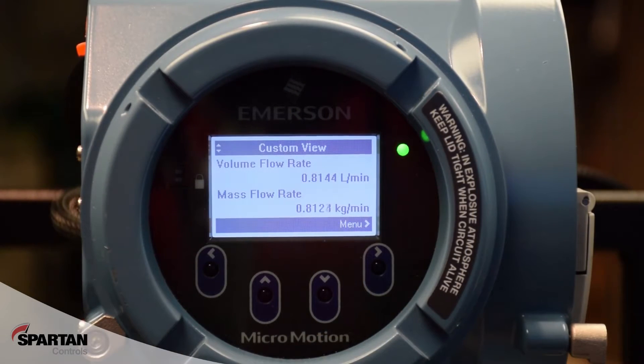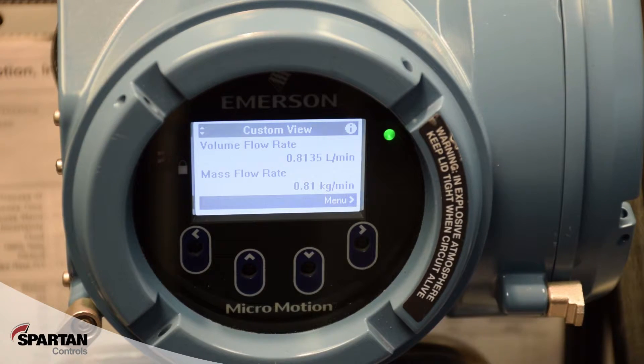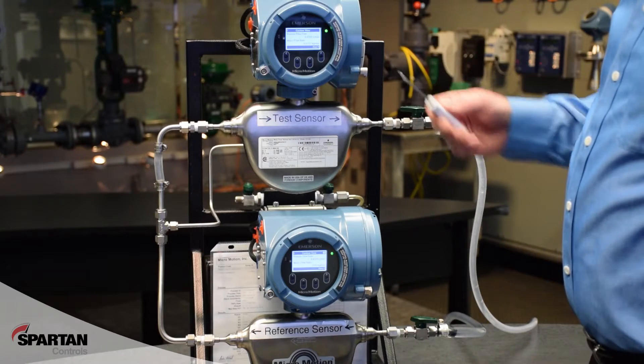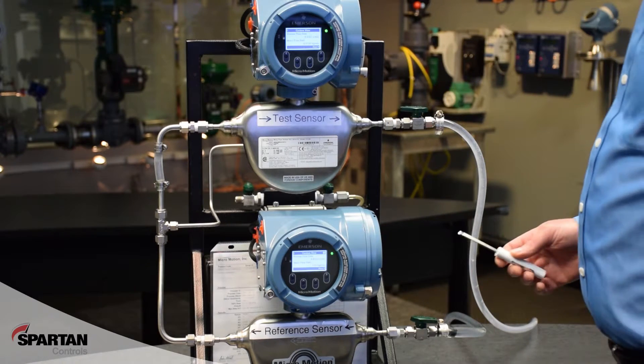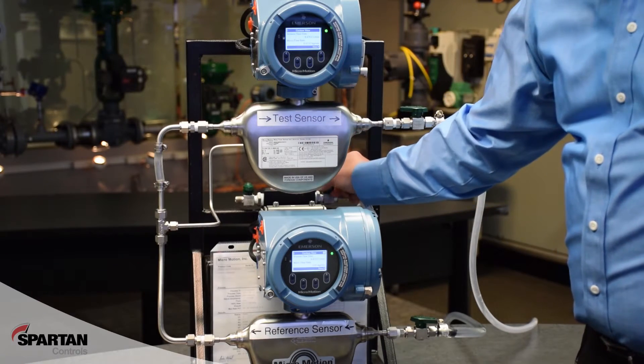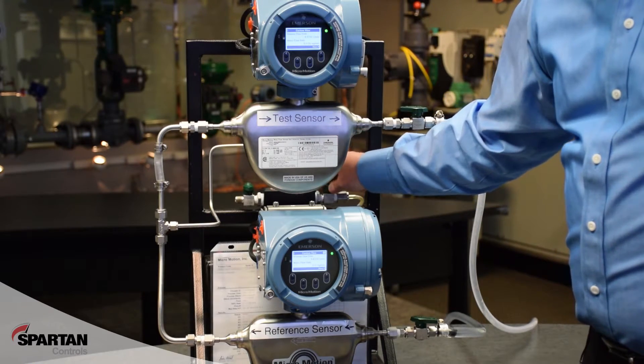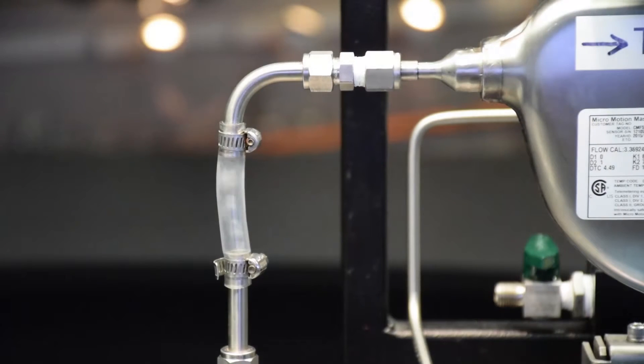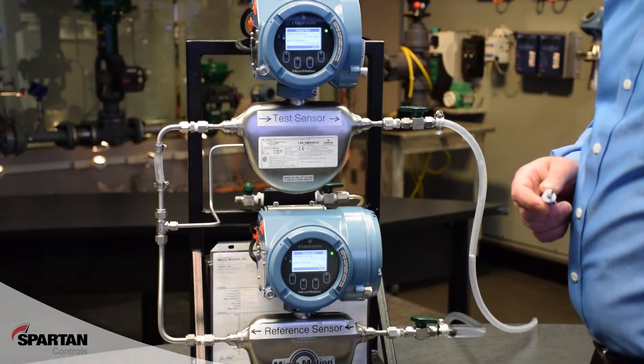Currently, I have flow going through both meters. It should be very close or similar flow, approximately 0.8 liters per minute, and I do not have any air being injected into the system. What I will do is start a test, and then as this test starts running, I will inject some air. You'll notice now I have those air bubbles being injected, and only my test sensor is going to see that entrained air. My reference sensor is just seeing the water.